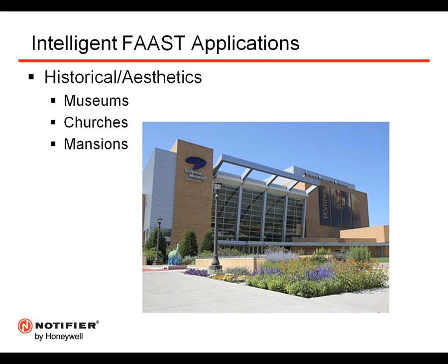Same thing could potentially hold true in mansions or high-end condominiums or those types of applications where, again, the concerned stakeholders, architects, and potentially the end user, the building owner, is concerned about the look of spot-type detectors in those settings. So they can use Aspiration, hide the pipes, and use those capillaries to come down and protect that space.